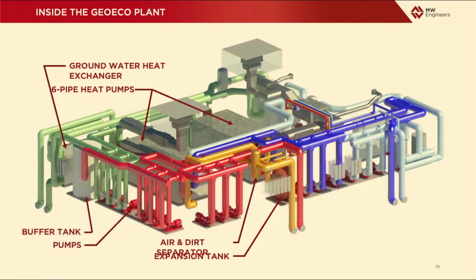And it's actually even protected through this heat exchanger. This heat exchanger has plates, and we'll look at an exploded view of this. It has a physical barrier between the water in the building and the groundwater, so there's no contamination of the groundwater. So there's no interface with that groundwater with actually the fluids in the plant. A buffer tank, so the buffer tank is a big tank that has a lot of additional volume, and what that additional volume does is it keeps equipment from having to turn on and turn off and turn on and turn off. The more volume you have in a system, the less those things have to cycle, and that cycling can really be detrimental to equipment life.